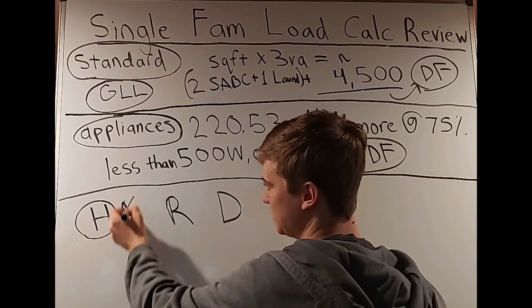You're going to see if you have your nameplate, and then you're going to go to table 220.55. You're going to see what your appliance is rated. You're going to find the column that corresponds with that, and then you're going to find the number of those appliances at that rating. Of course, if they're all at different ratings, they're all going to be individual. So if you have 2 appliances at the same rating, let's say they're 8 kilowatt, you're going to use column B, and since you have 2 appliances, you're going to get 65% when you line those both up.